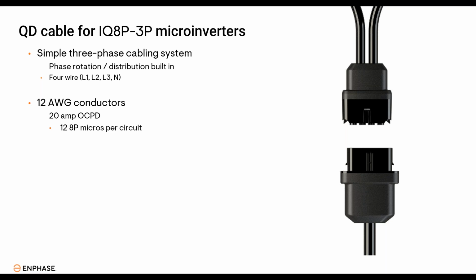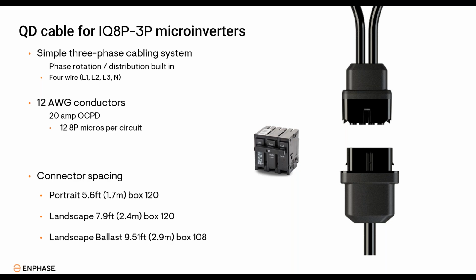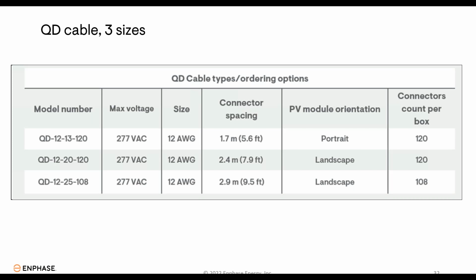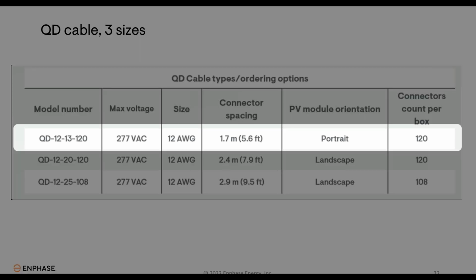Like I mentioned, it has 12 AWG conductors inside of the cable. Each circuit will get connected to a 20 amp 3-pole breaker inside of that sub-panel board. And there are 12 IQ8P 3P microinverters per each circuit. There are 3 different sizes or lengths of the QD cable, and that's all dependent on connector spacing.